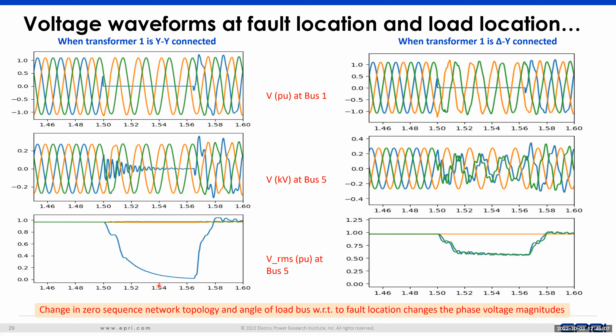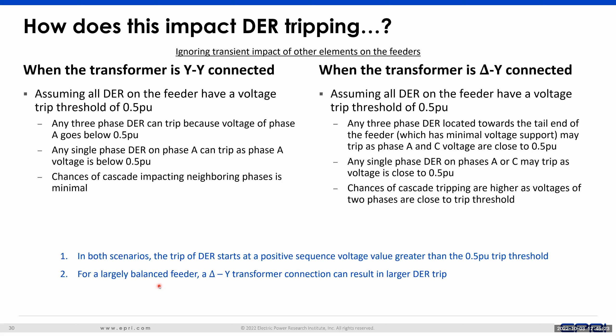And we can essentially assume that if we make an assumption of the percentage of spread of DER across various phases, we can make a determination of how much DER would trip, what kind of voltage level we should derive, and so on. And we have done that to understand how to parameterize these aggregated models for unbalanced behavior or unbalanced faults. And here is the same kind of example as we had seen before, wherein detailed distribution simulation results are compared against an aggregated behavior, essentially showcasing that the aggregated model could represent the behavior for unbalanced faults.